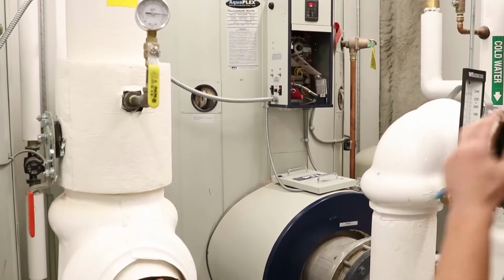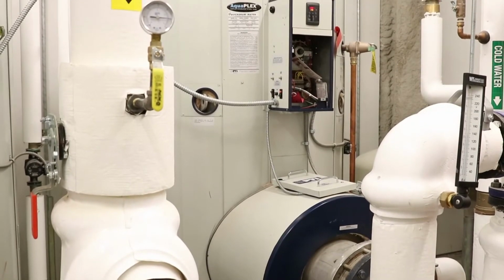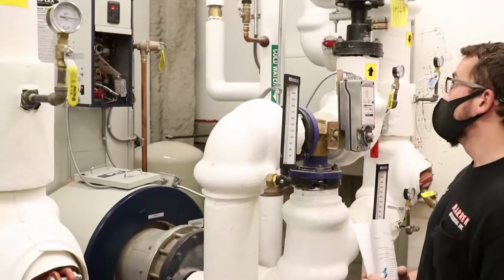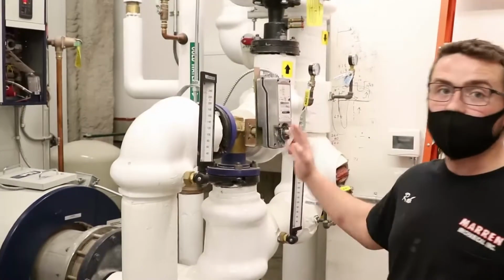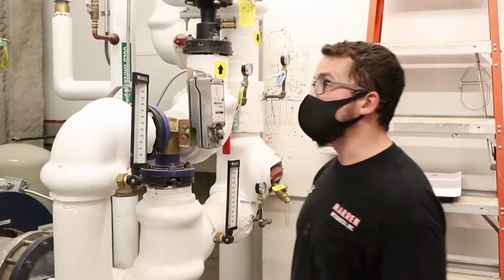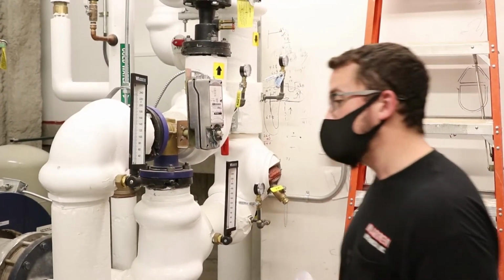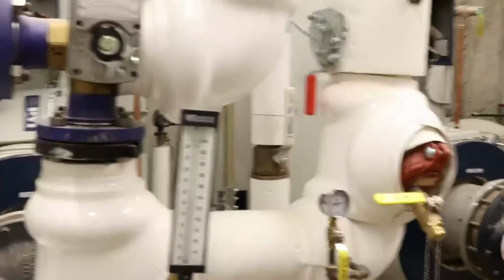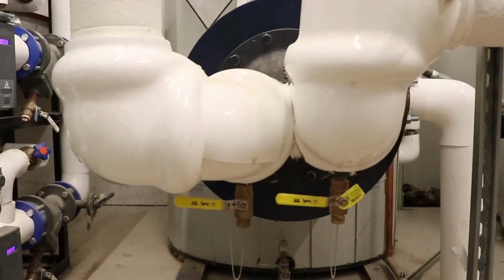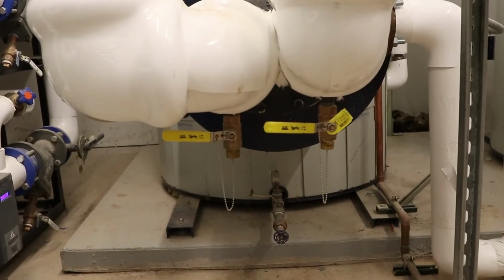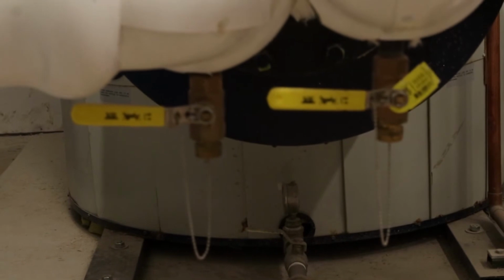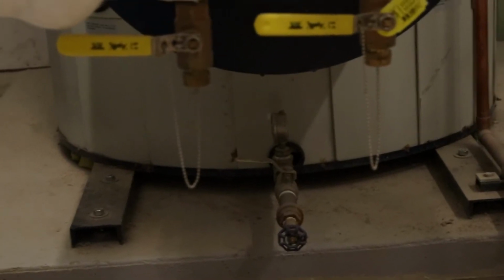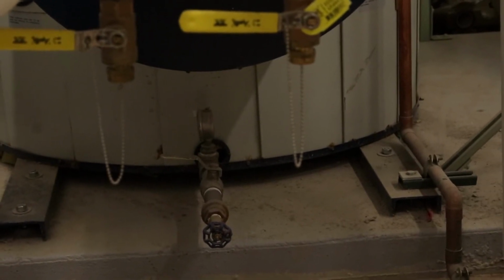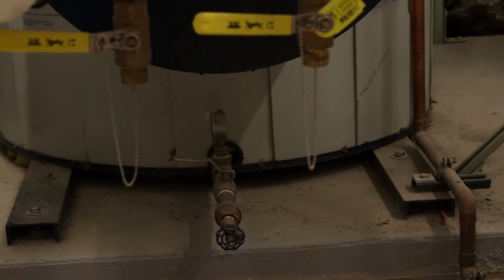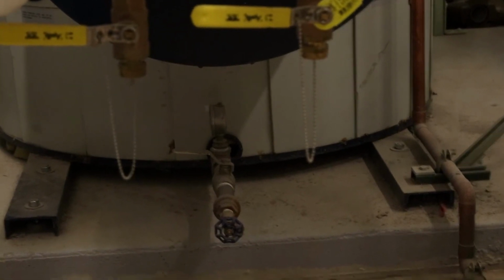And then we'll talk about the flushing of the tank. So if you're at a point where the water heater is performing poorly, and other causes, control issues, control failures have been ruled out, you'll want to try to flush the tank. An initial way that you can try to do this is to walk up, and underneath each heat exchanger you'll see a pressure gauge followed by a manual ball valve. You open that valve, that is your tank drain. You'll want to open that drain for about 10 seconds and take note of the water coming out. If the water coming out is dirty, you should repeat until that water clears up. If that water does not come out dirty and you are having issues with a dirty tank, then you may need to go further as far as the flushing procedure.